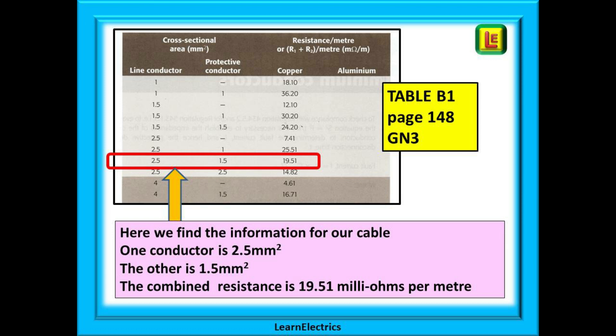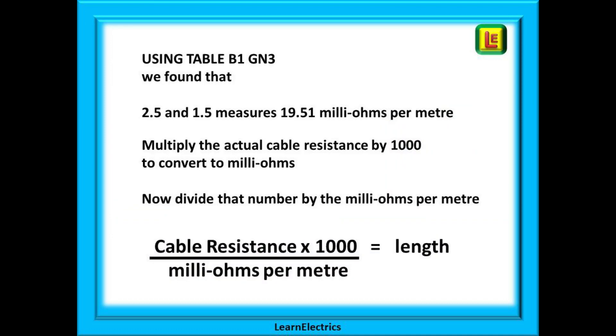Using the table we found that 2.5 twin and earth with a 1.5 earth has a resistance of 19.51 milli ohms per meter length. We measured the cable in ohms yet the table is in milli ohms they don't match. We need to make them the same units. So multiply the measured resistance by 1000 and now everything is in milli ohms. Divide that number by the milli ohms per meter to give you the length.